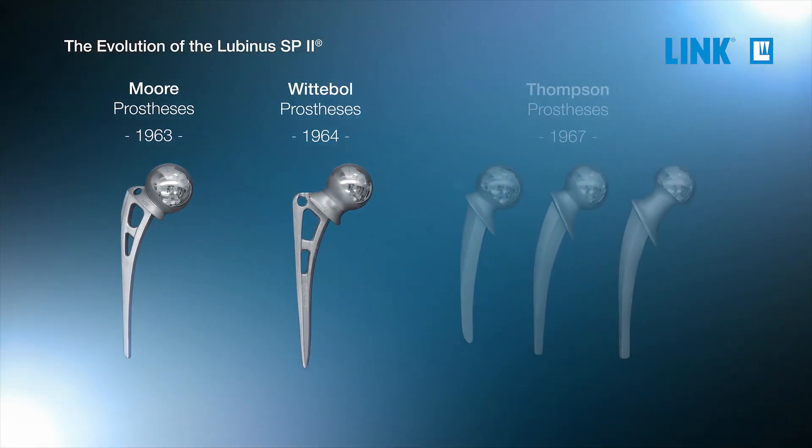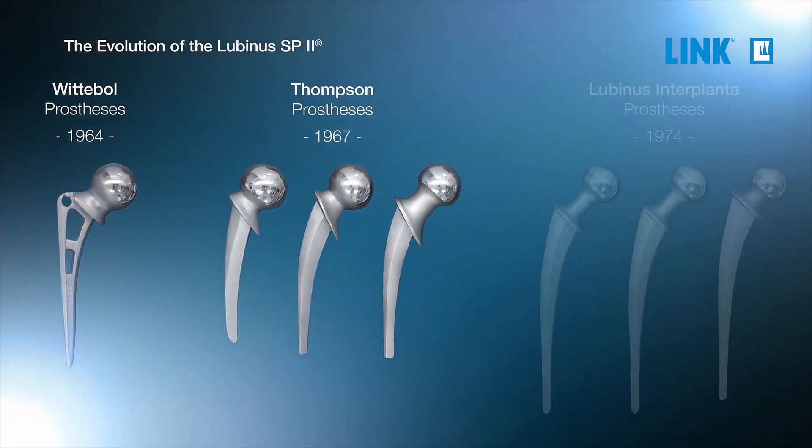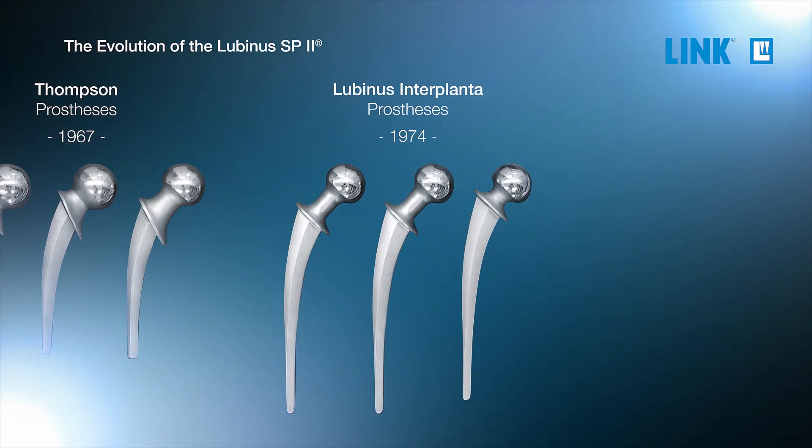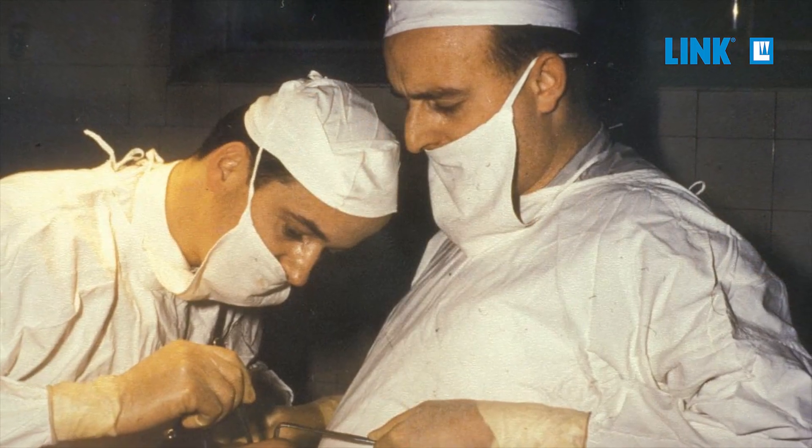That later changed with the Thompson prosthesis, which had three different sizes available. The first own development of an implant at the Lubinus Hospital started back in 1974 with the Lubinus Interplanta stem, which at the time still had the diamond shape of the stem common at those days. A couple of years later, the first aseptic loosening occurred, and it turned out that one problem would be the fixation of the cement in the bone or fixation of the implant in the cement.